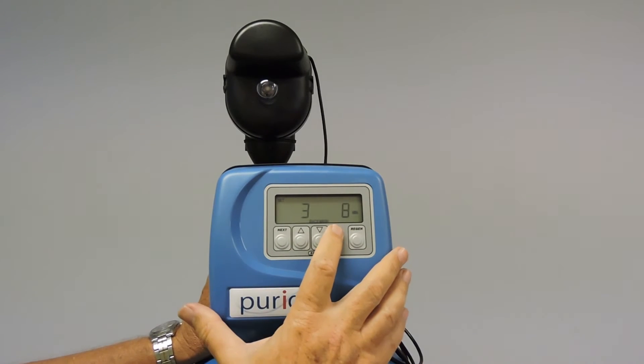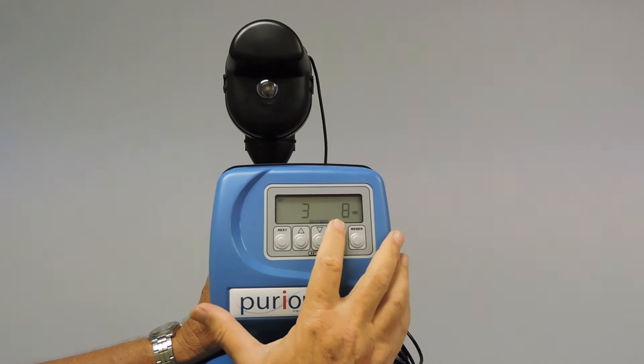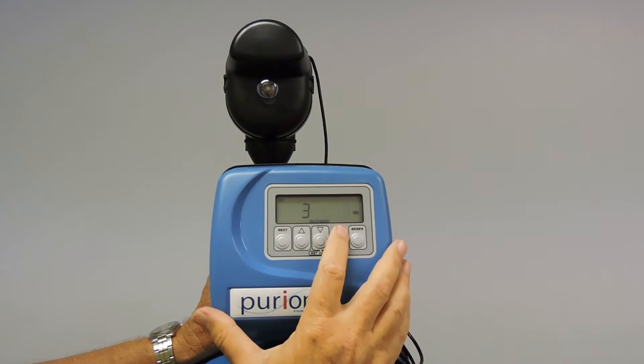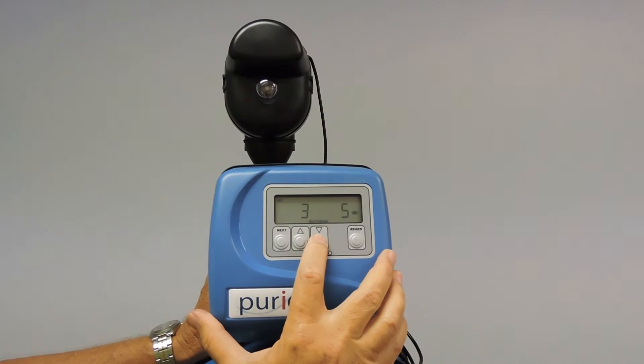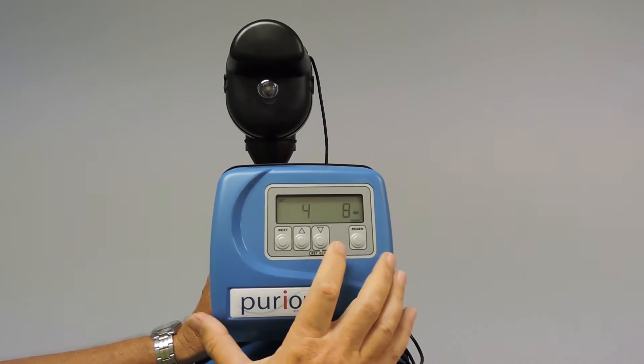Accept. Third step is our second backwash. And we use half the flow rate of the first backwash to achieve this. So we want to bring this one down to four minutes. So we will go down to four. Accept.